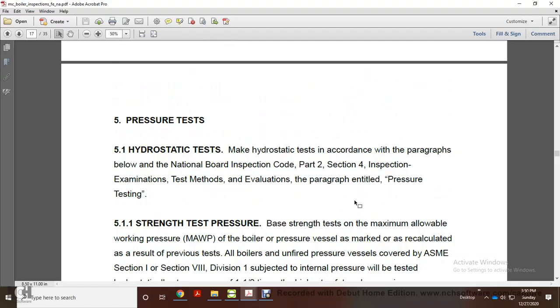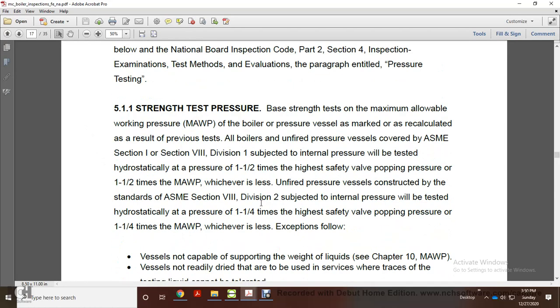Alright, 5. Pressure test. Hydrostatic test. Make hydrostatic tests in accordance with the paragraphs below of the National Board Inspection Code, Part 2, Section 4, Inspection, Examination, Test Methods, and Evaluation, paragraph Pressure Testing. Strength test pressure: base the strength test on the maximum allowable working pressure of the boiler or pressure vessel as marked, or as recalculated as a result of previous tests.